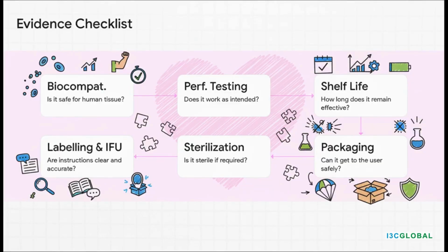Well, it's a whole lot. You got to prove biocompatibility. Is it safe to be in or on a human body? You have to do performance testing. Does it actually do what you say it does? You got to figure out its shelf life. How about packaging and shipping? Can it get to the hospital without being damaged? And if it's supposed to be sterile, you better have proof that your sterilization process is rock solid.